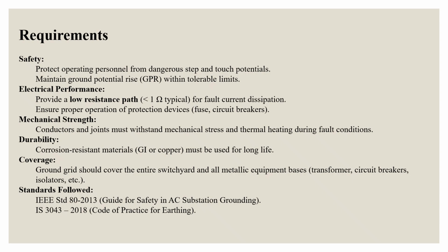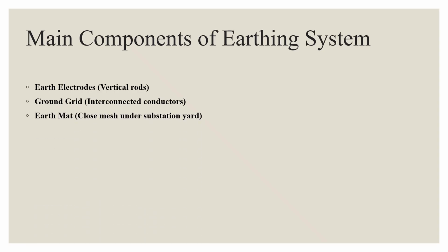The design follows IEEE standard 80-2013 and IS 3043-2018. The earthing system is made up of several components. This includes earth electrodes like vertical rods. The ground grid consists of interconnected conductors and the earth mat under the substation surface. We also have earthing leads connecting equipment to the grid and enhancement materials like charcoal that improve soil conductivity. All these components work together to maintain a low resistance path to earth.